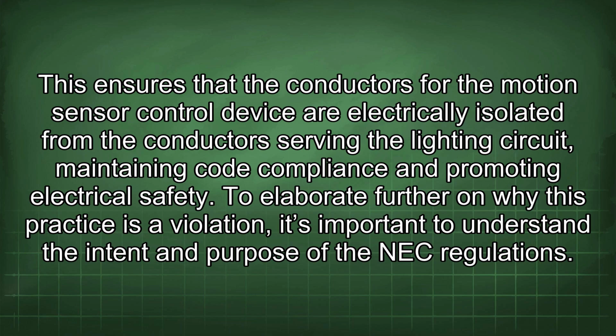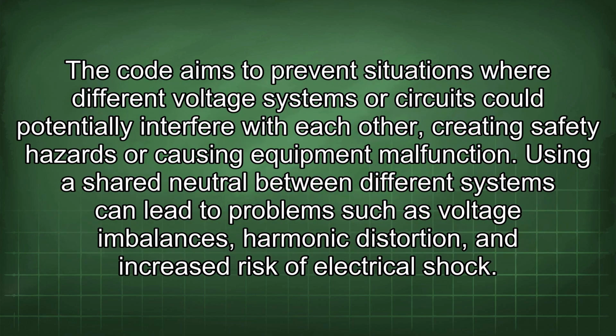To elaborate further on why this practice is a violation, it's important to understand the intent and purpose of the NEC regulations. The code aims to prevent situations where different voltage systems or circuits could potentially interfere with each other, creating safety hazards or causing equipment malfunction. Using a shared neutral between different systems can lead to problems such as voltage imbalances, harmonic distortion, and increased risk of electrical shock.